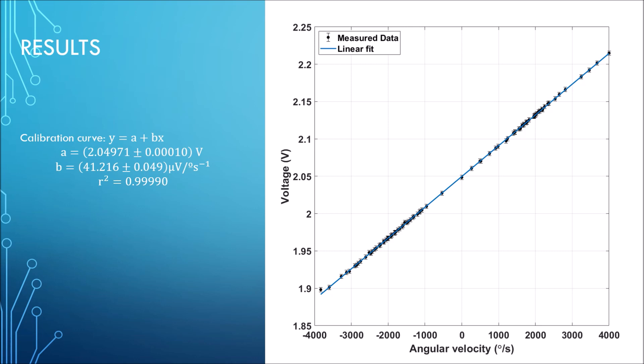This is the calibration curve. All these black dots are measurements showing the voltage output for both positive and negative angular velocities - that's clockwise and anticlockwise rotation. From the fit we can get the sensitivity, and this is a very linear fit because r-squared is so high. I'm very happy with these results.